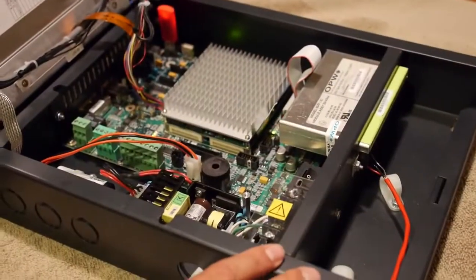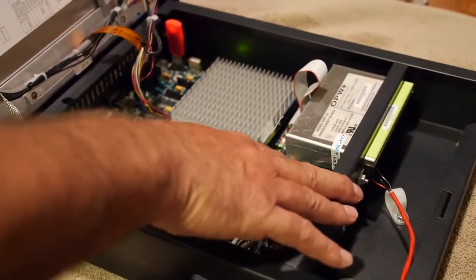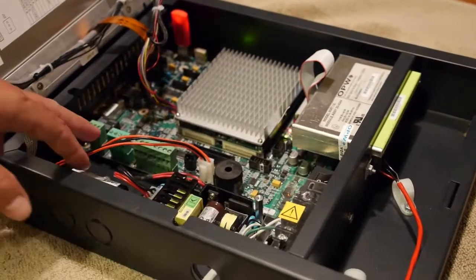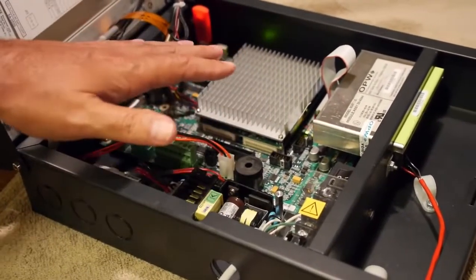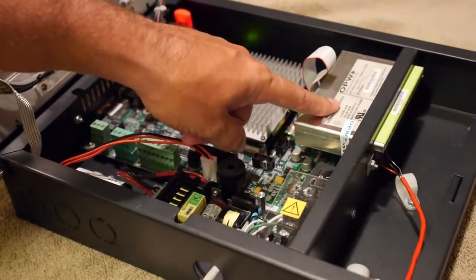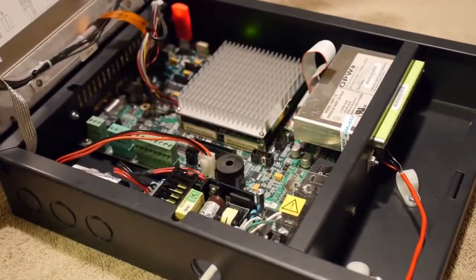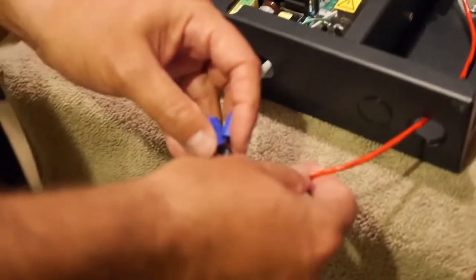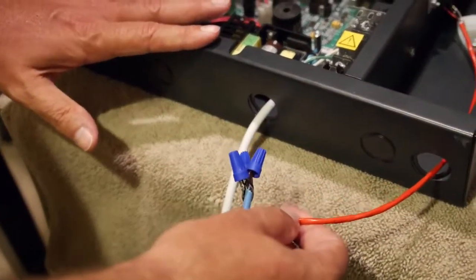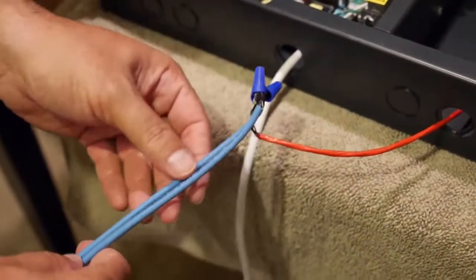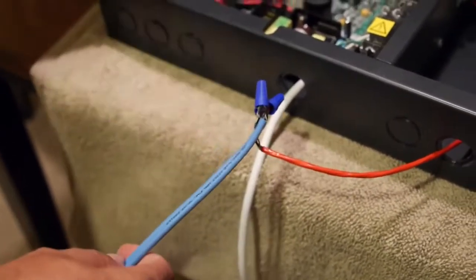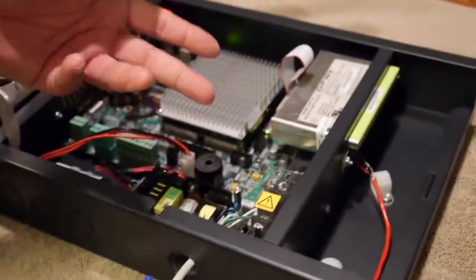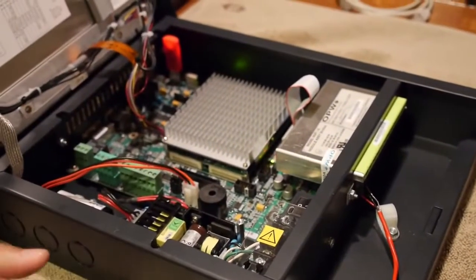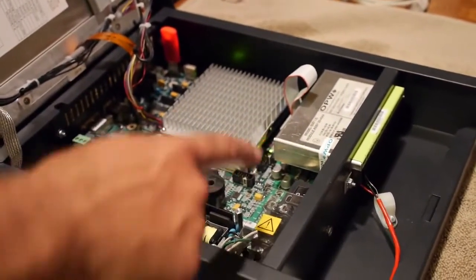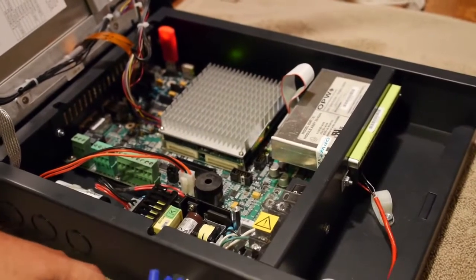One of the things you can do is come into the console and turn power off. The lithium battery will continue to power the main board and the CF card, but it drops power to the barrier itself. At that point, you can go out in the field and redo your splices without worrying about blowing the barrier. But you're only going to have about 7 to 10 minutes to get this done. In any case, the unit will power completely down, and then you'll have to go through a complete reboot coming back.